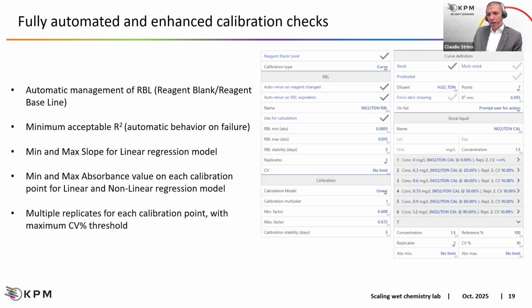What about data reliability? Today, we could be prone to human errors while running the testing. We already saw that with SmartChem, we can fully automatize the analytical process, but by doing the proper settings in the software, we can also have a fully automated enhanced check for the calibration. Why? Because we can define automatic management of the RBL, which is the reagent baseline. So with the RBL, we can determine what is the absorbance of the reagents in the total reaction volume. And this value can be removed from the final color we will read from the cuvette at the end of the incubation.